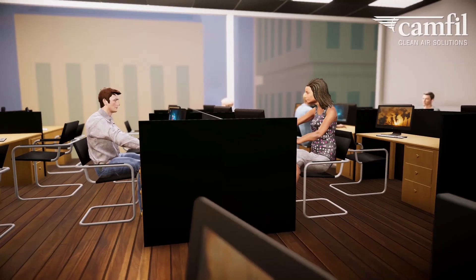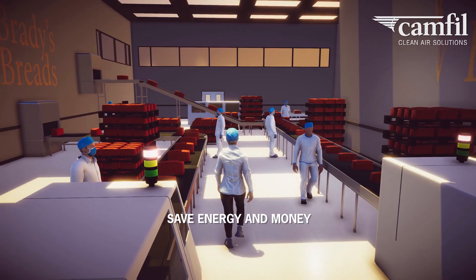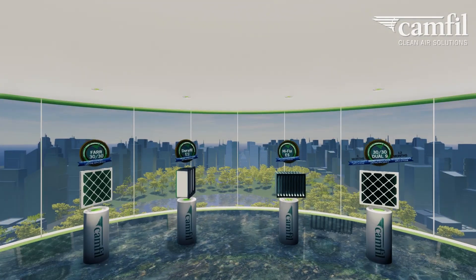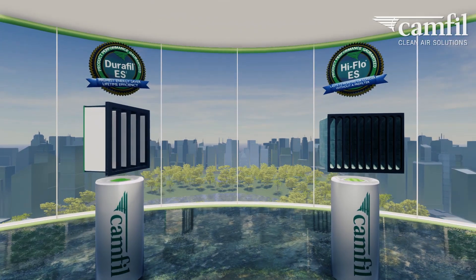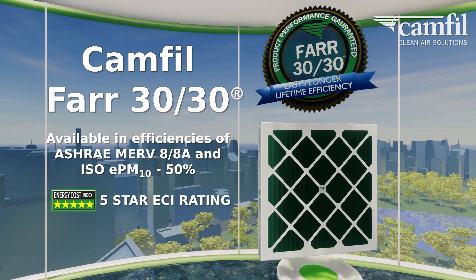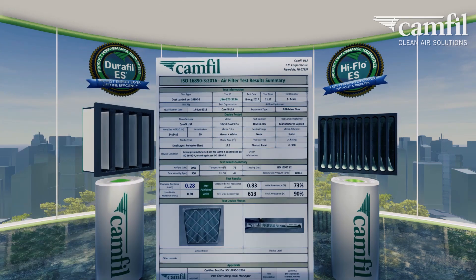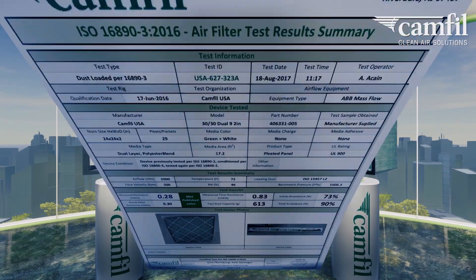Using the right air filter will not only help you to maintain healthy indoor air quality, it will help you to save energy and money. Filters are available today to meet the stricter demands for removing PM1s, such as CAMFIL's Durafil ES2 and Hi-Flo ES air filters. ISO 16890 has been introduced to help understand how efficient your air filter is against a range of particle sizes. To best understand your filter's efficiency, always check the test report.